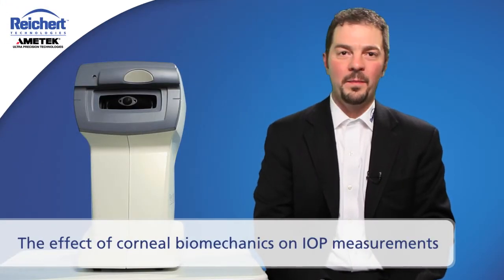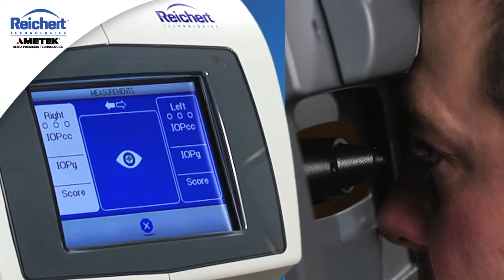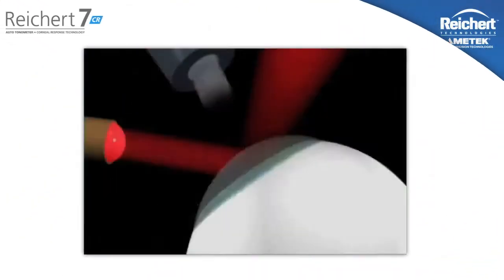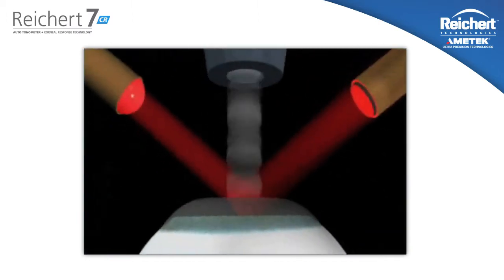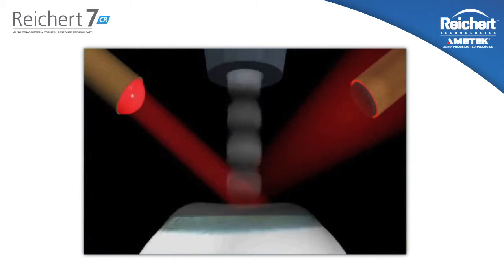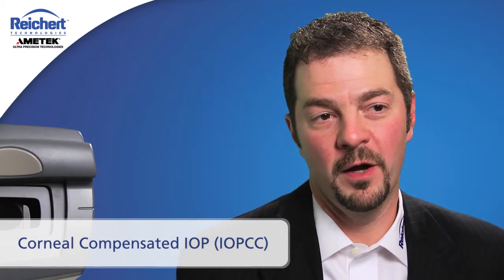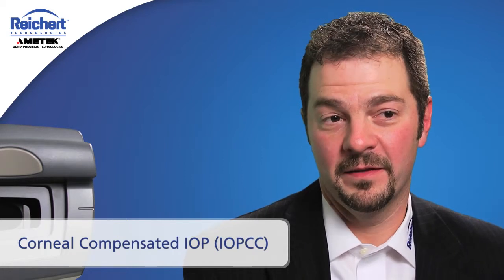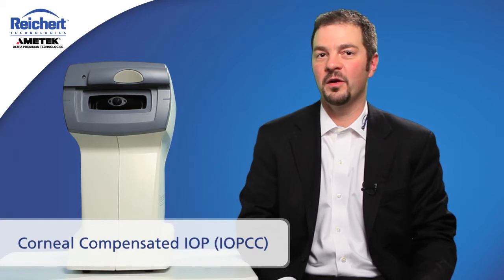The Reichert 7CR utilizes a dynamic bi-directional applanation system to quantify the biomechanical properties of the cornea. Corneal biomechanics is really what influences the accuracy of tonometry measurements. As the air jet impinges upon the cornea, the cornea moves back towards applanation, and the system registers a signal peak upon the inward applanation. Then the cornea becomes indented, causing the air pulse to reduce in velocity. As the cornea returns to its original radius of curvature, it passes through a second applanation and registers the pressure a second time. As the cornea moves rapidly inward and outward under the air pulse, it develops a dynamic corneal resistance — a damping effect. We quantify that effect by a measurement known as corneal hysteresis.